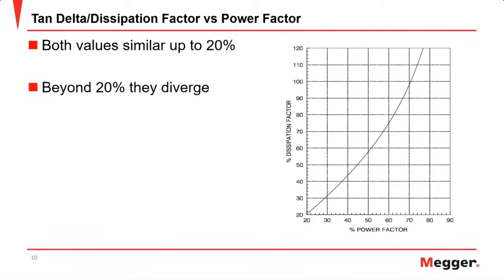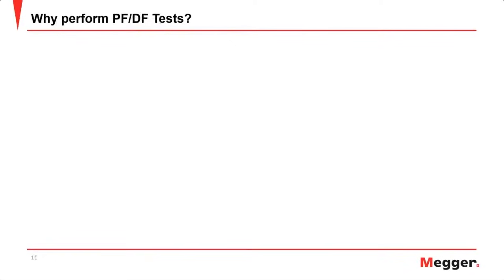And anybody who's been doing power factor or dissipation factor will tell you that 20% is clearly in the area where something is catastrophically wrong. So for all intents and purposes, when you're looking at dissipation factor or power factor at levels between 0 and 2%, they are going to be almost exactly the same. And using the term tangent delta or dissipation factor versus power factor, it should be understood that, again, those are exactly the same.